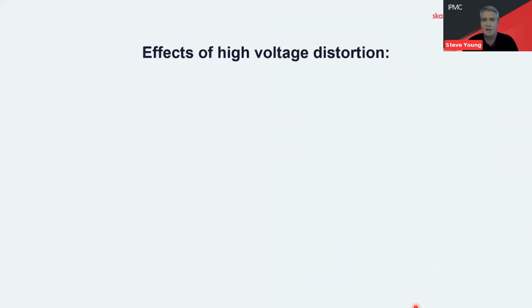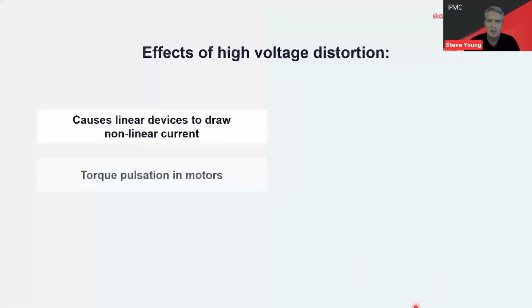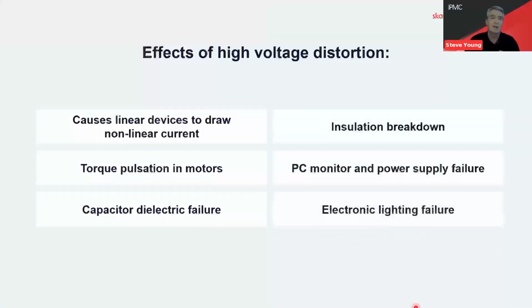And we can see on the next slide some information and some manifestations, if you like, of typical effects of high voltage distortion. We've got even linear, this is non-harmonic load, starting to draw that distorted non-linear current, so adding heat and vibration, torque pulsation in motors almost trying to drive themselves backwards. This interaction that I alluded to with capacitors, as well as voltage disturbance, insulation stress, and of course, untimely failure of key items of load-bearing equipment like power supply units and electronic lighting. And of course, that list isn't exhaustive. So what can we do about it?